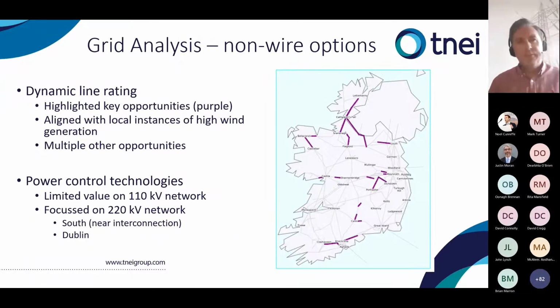We also examined the effect of other types of technologies not yet in use on the system, in particular dynamic line rating and power control technologies. For dynamic line rating, we highlighted the main opportunities in the Northwest, where lines are already uprated, but there are plenty of other potential candidates throughout the country. In general, dynamic line rating should provide more capacity throughout the year.